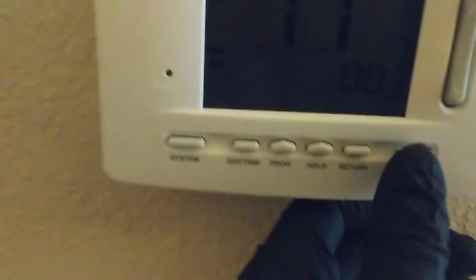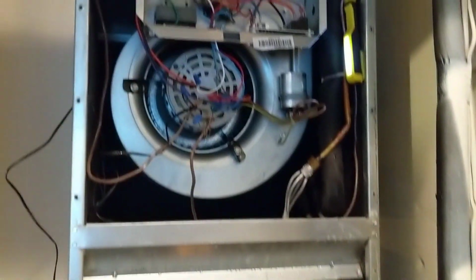It locks on. Just unhook your low voltage over here and all your high voltage wires over here. Alright, we got the new board in, it's all wired up. So now, put the disconnect back in. And we'll set the thermostat to fan on, see if it fires.